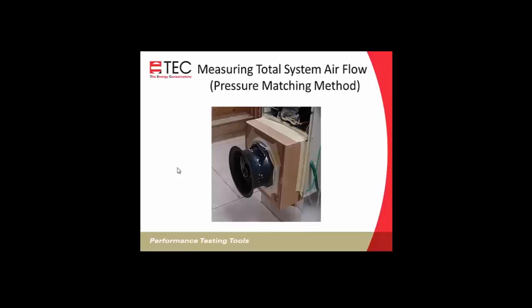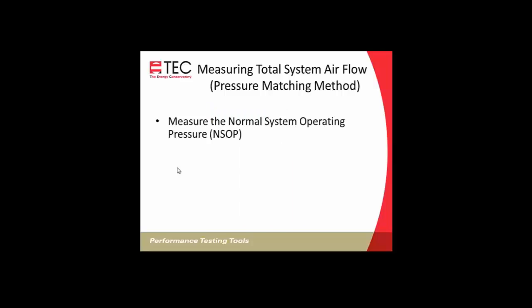Next, we'll be talking about measuring total system airflow using the pressure matching method with the Duct Blaster fan. And for the procedure, you'll want to first measure the normal system operating pressure.